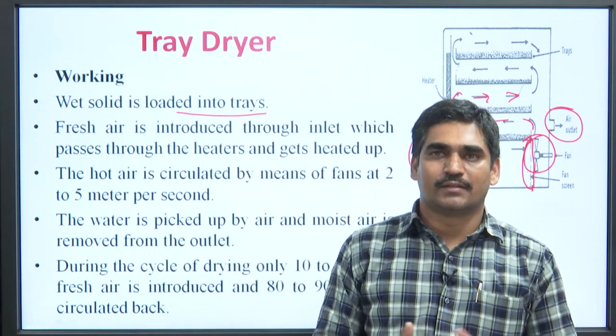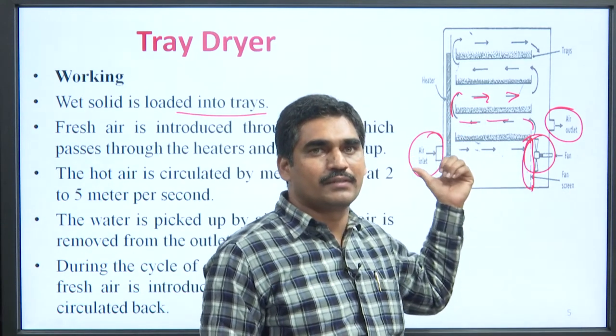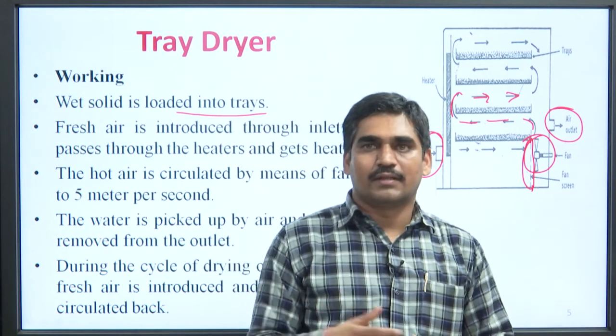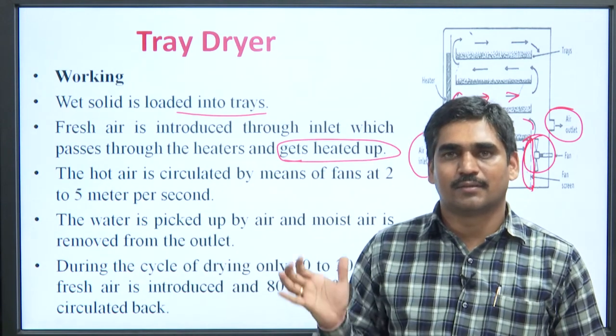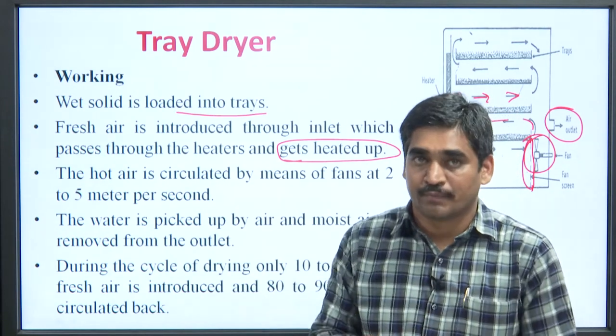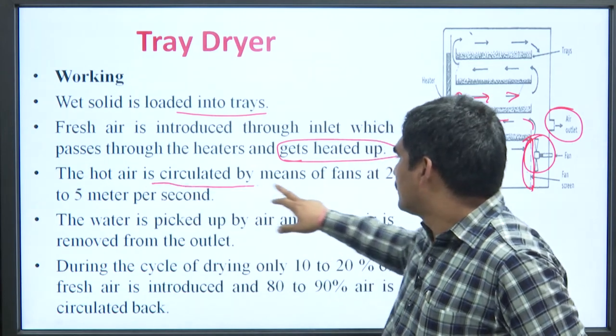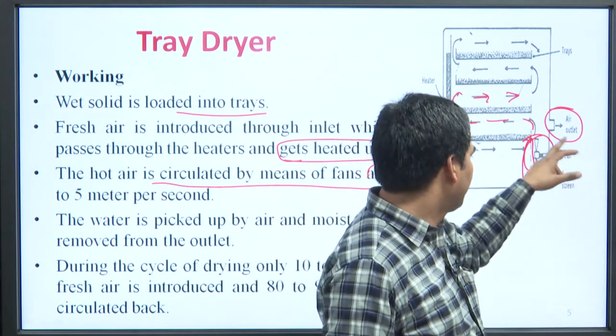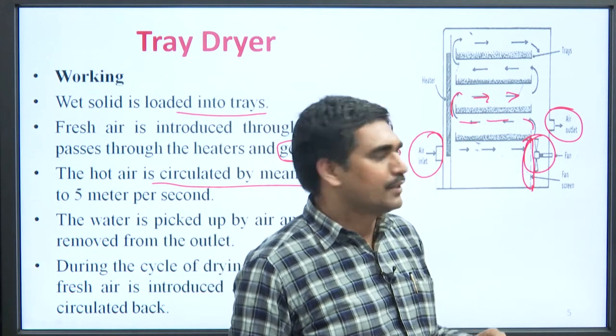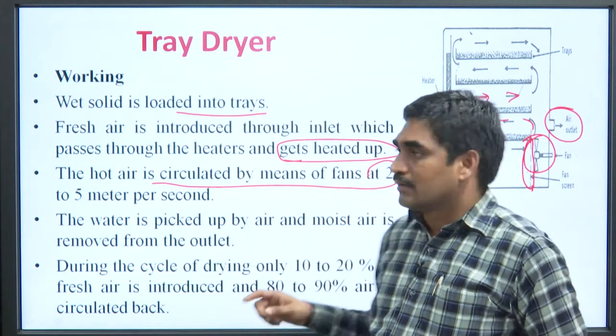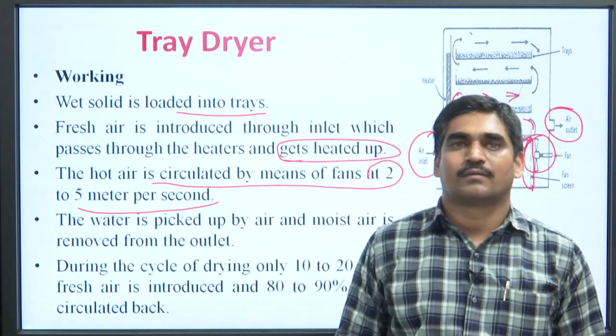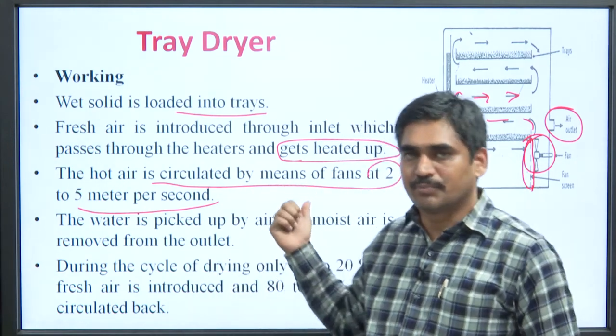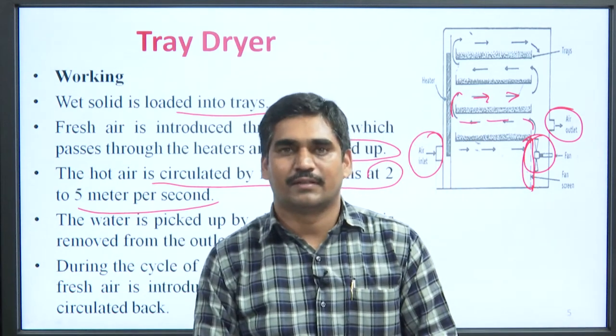Fresh air is introduced through the air inlet and passes through the heater, where it gets heated. As the fresh air passes over the heater, it gets heated. This hot air is then circulated by means of a fan. The speed of this fan is 2 to 5 meters per second, at which the hot air is circulated inside the tray dryer.